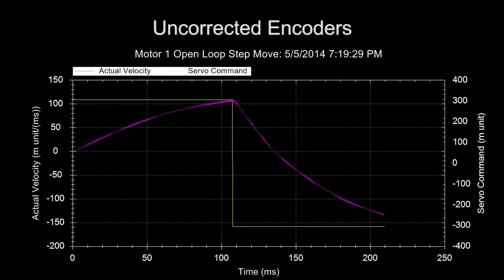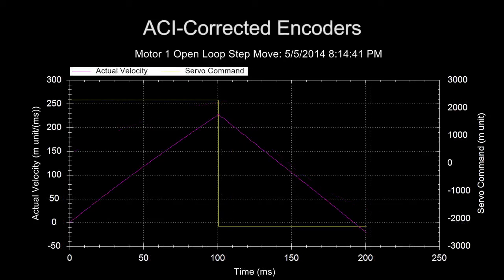Each deviation can cause position calculation errors and nonlinearities, which produce torque ripple, velocity ripple, and ultimately vibration on the axis. By eliminating these nonlinearities, we can guarantee a much smoother velocity profile, which permits more reliable, vibration-free moves.